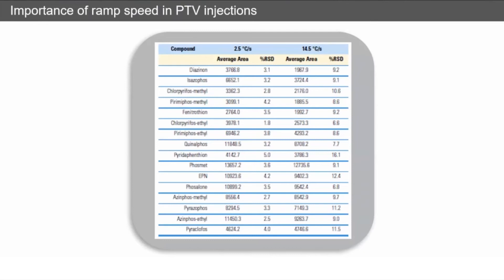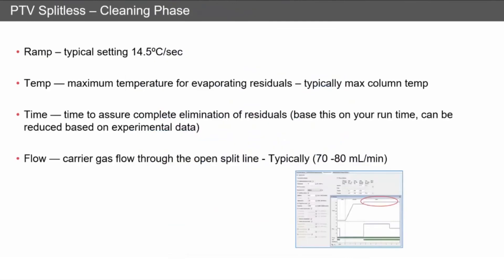Always keep this ramp speed down on the splitless injection. Finally, there's a cleaning phase. This is something you don't have in a split/splitless inlet. We can ramp that inlet temperature up to clean it and get rid of any high boilers. We don't care about the speed at which it heats up, so we typically go with our highest settings, around 14.5 degrees per second, and we want to go to the maximum temperature to get rid of residuals, typically the maximum column temperature.